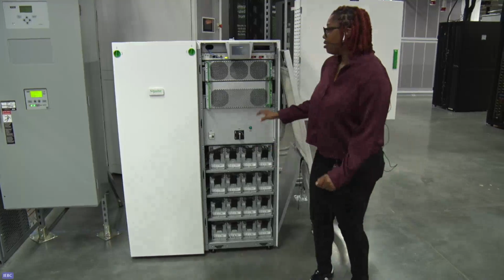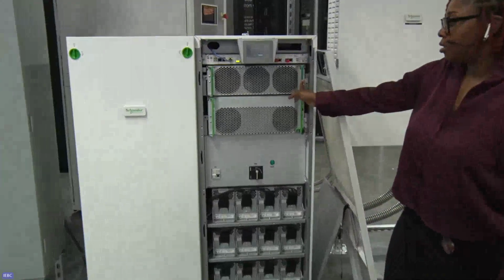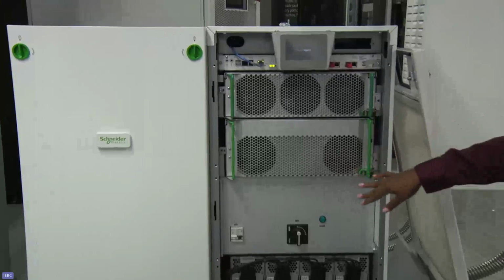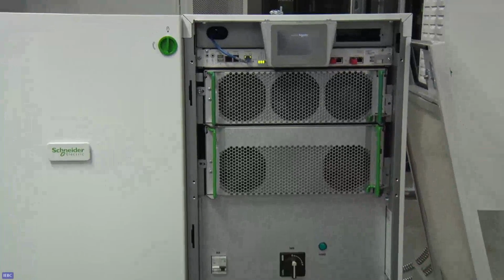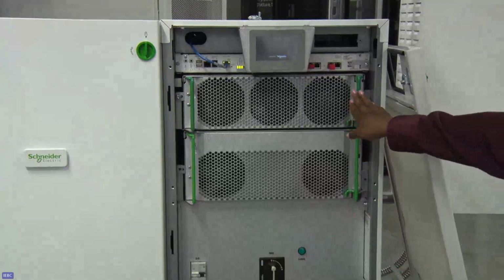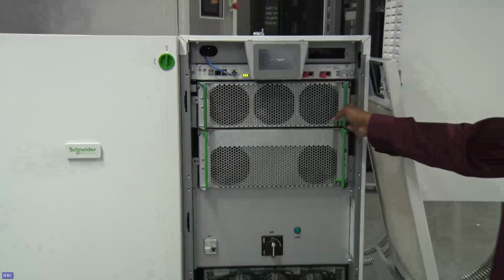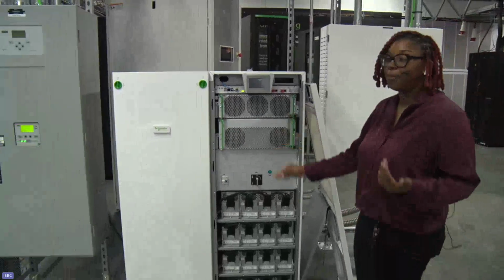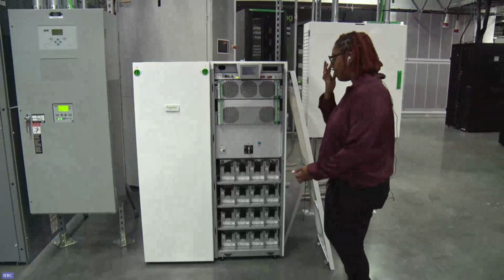So if you notice, there's only one power module here. This is our static switch. The static switch was also in that standalone, but one 50 kW power module, or 25 kW power module, same thing, can either output 480 volts or 208 volts.